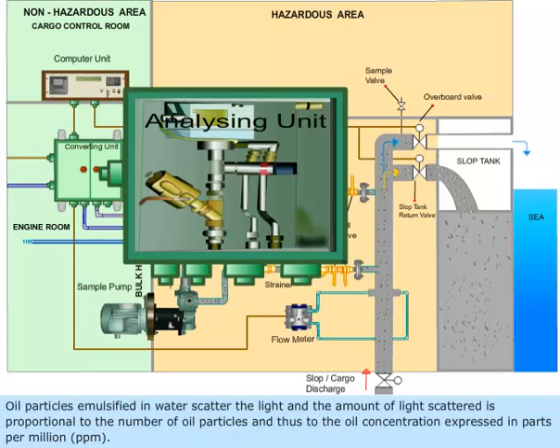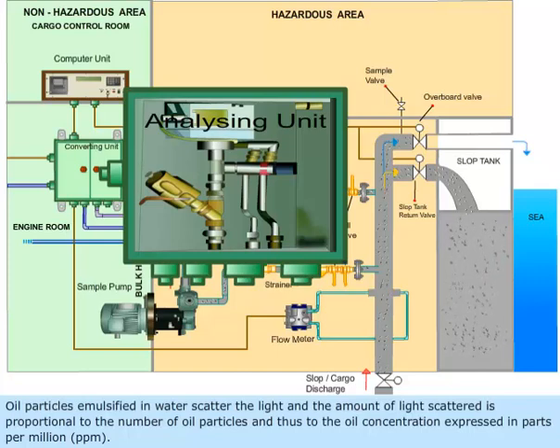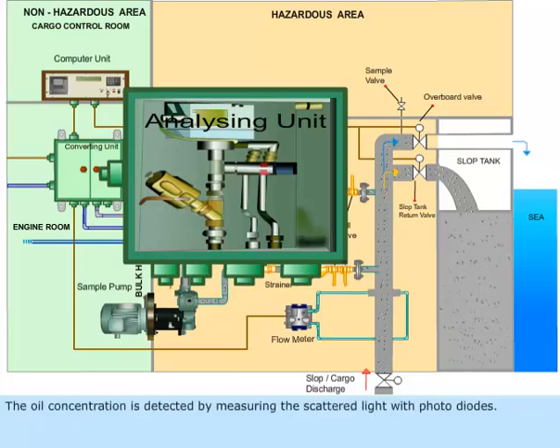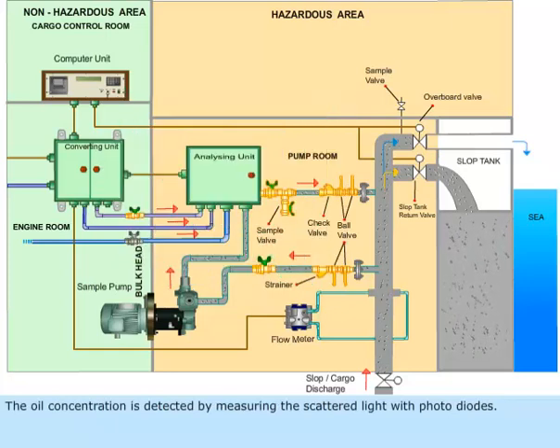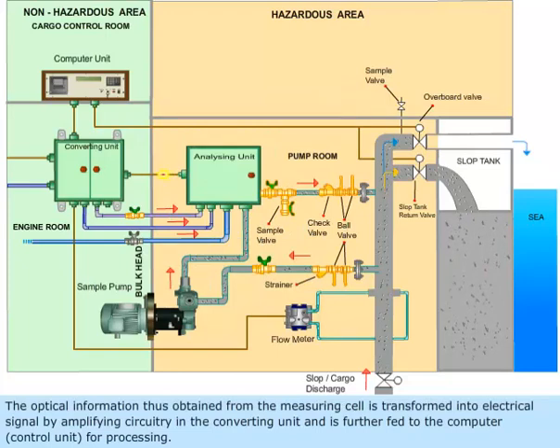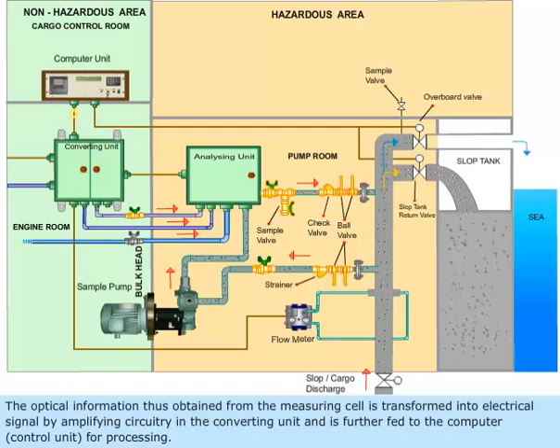Oil particles emulsified in water scatter the light, and the amount of light scattered is proportional to the number of oil particles and thus to the oil concentration expressed in parts per million (ppm). The oil concentration is detected by measuring the scattered light with photodiodes. The optical information obtained from the measuring cell is transformed into an electrical signal by amplifying circuitry in the converting unit and is further fed to the computer control unit for processing.